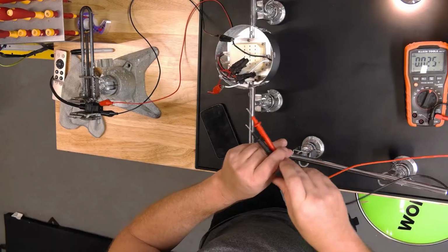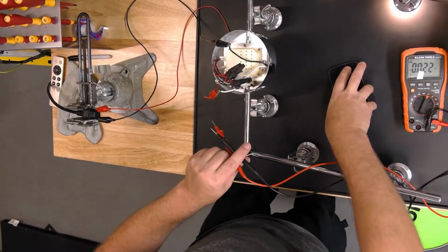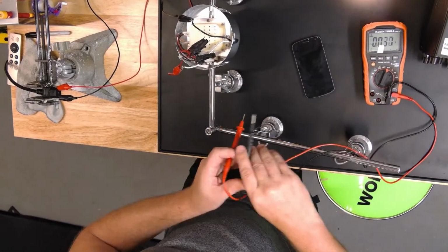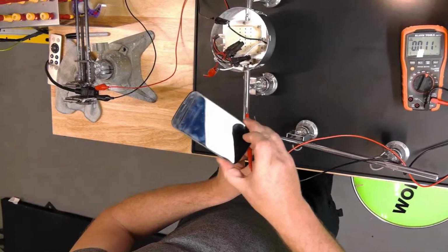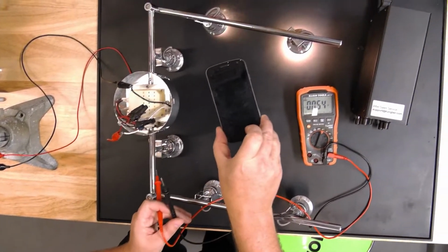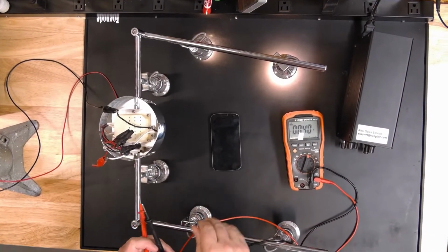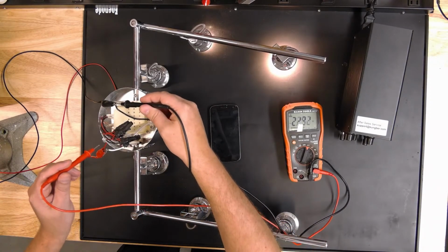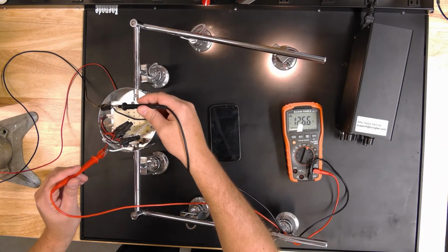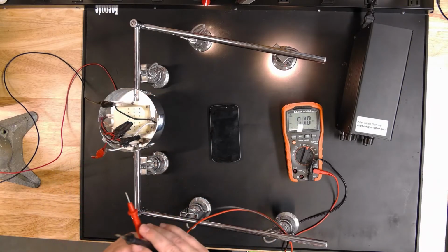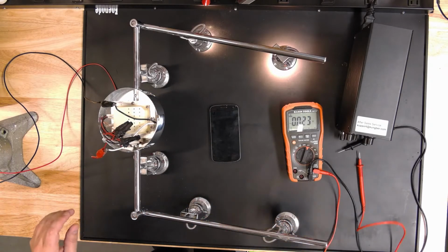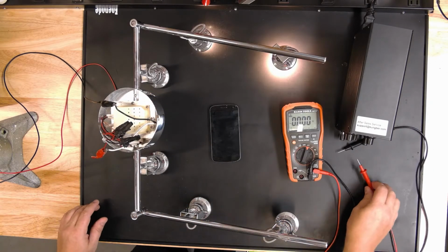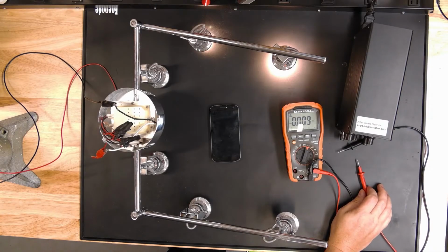So I am getting some sort of power here. Go ahead and take a measurement just to be sure. There we go. We'll work through it. Measurement here, and here. 126.6 volts AC. And like I said, that is isolated, so it's not going to be the 120 volts that you normally think it is.